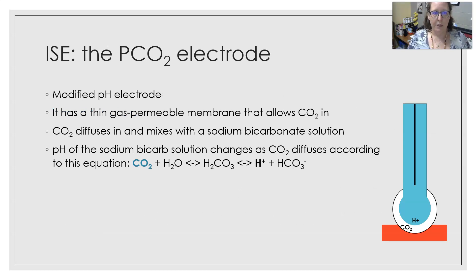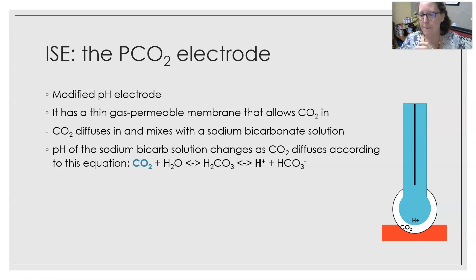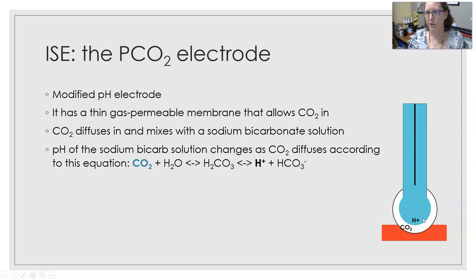A modified pH electrode is the pCO2 electrode — a gas sensing electrode. It has a thin gas-permeable membrane that allows CO2 in from the sample. The CO2 crosses over the gas-permeable membrane and interacts with a sodium bicarbonate solution, which causes a chemical reaction. As CO2 interacts with the sodium bicarbonate solution, the pH changes to produce hydrogen ions. The hydrogen ions then cross a second membrane — the glass membrane permeable to hydrogen ions only — and are then read. So it is essentially a pH electrode with an extra membrane permeable to CO2.